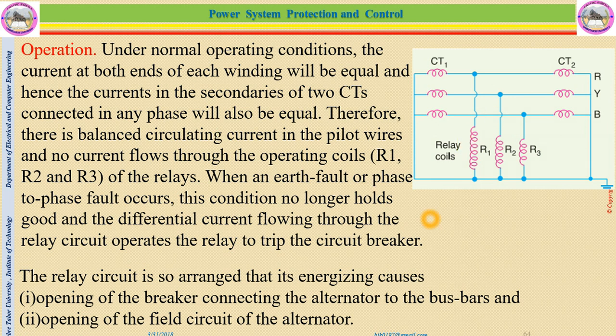When an earth fault or phase-to-phase fault occurs, this condition no longer holds good, and differential current flows through the relay circuit and operates the relay to trip the circuit breaker. So if CT1 and CT2 are not equal, that means due to a ground fault or line-to-line fault, there will be some current which passes across R1, that is, in relay coil 1.